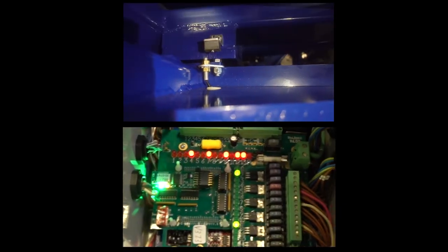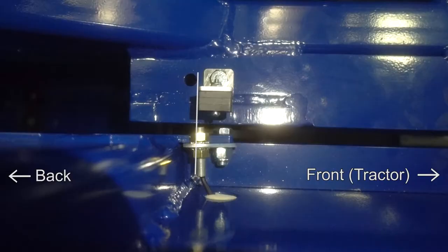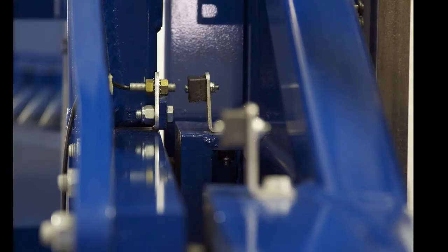This reed switch should line up with the back edge of the stack of magnets located toward the front of the machine. There should be a 3/8 inch air gap between the end of the reed switch and the flat surface of the closest magnet.